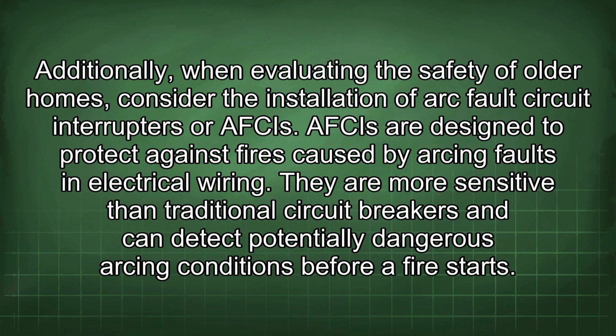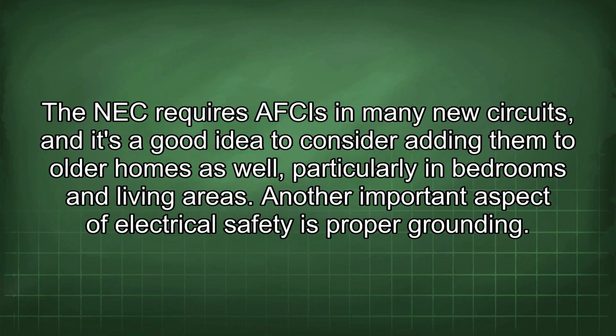Additionally, when evaluating the safety of older homes, consider the installation of arc fault circuit interrupters, or AFCIs. AFCIs are designed to protect against fires caused by arcing faults in electrical wiring. They are more sensitive than traditional circuit breakers and can detect potentially dangerous arcing conditions before a fire starts. The NEC requires AFCIs in many new circuits, and it's a good idea to consider adding them to older homes as well, particularly in bedrooms and living areas.